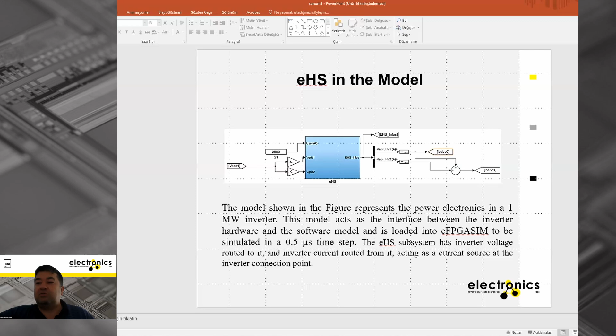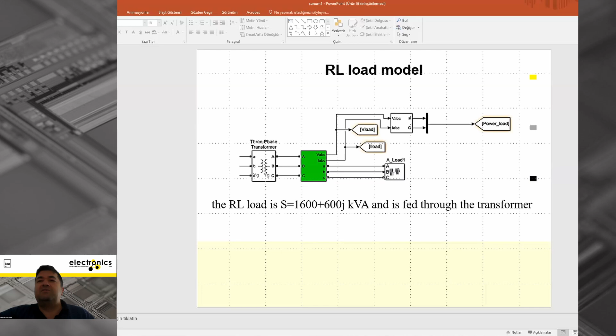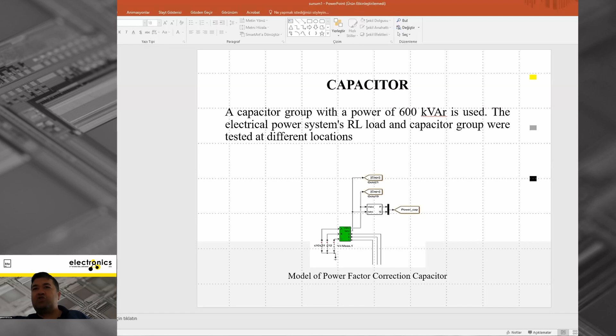This is our RL load model, which is a three-phase transformer, and it has 1,600 kW active power and 600 kVAr reactive power, and is fed through the transformer. And our capacitor bank has a power of 600 kVAr. The electrical power system, RL load, and capacitor group were tested at different locations. And in the study, we used 9 scenarios to determine which condition is worst in terms of the transient voltage.